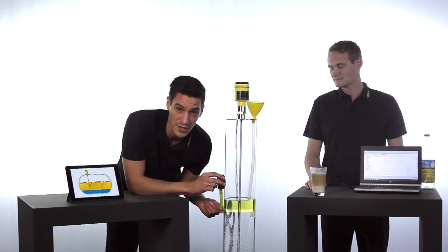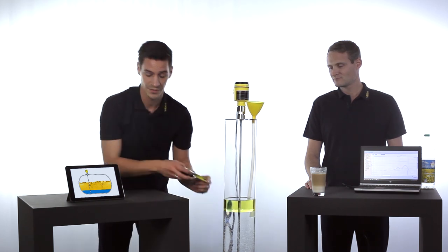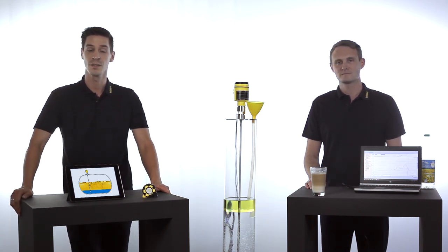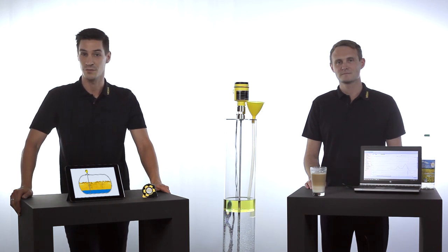It is 5 centimeters, which means that the VegaFlex series 80 can distinguish the two media beginning from a minimum layer thickness of 5 centimeters. That's world-class performance and gives you the safety for reliable measurement.